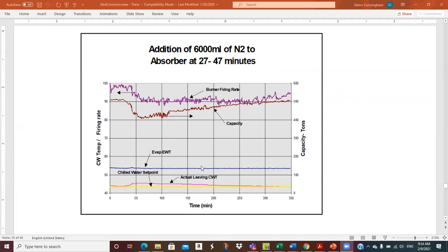Okay, so air goes in the machine in this period. We see capacity drop, which is what you would expect because the pressures are going up in the machine. The temperatures are going up at the evaporator, so we get less capacity. And we can see down here, our chill water set point is the same, looks like maybe 44, 43, 44 degrees. And we were right on set point, and then the air came in, and because the capacity went down, the leaving chill water temperature went up, looks like maybe 2 degrees, something like that.